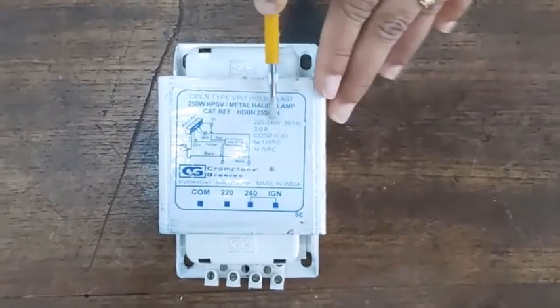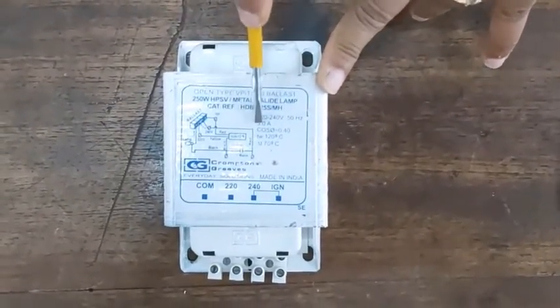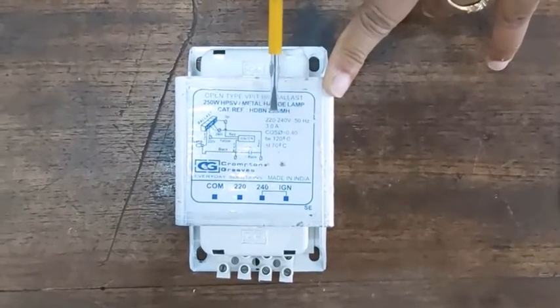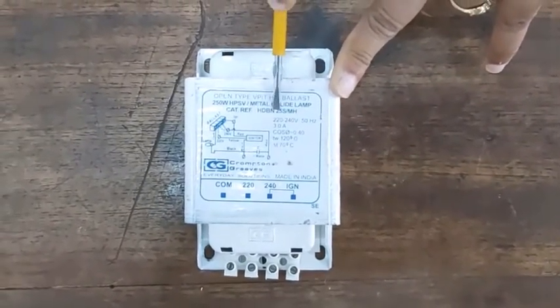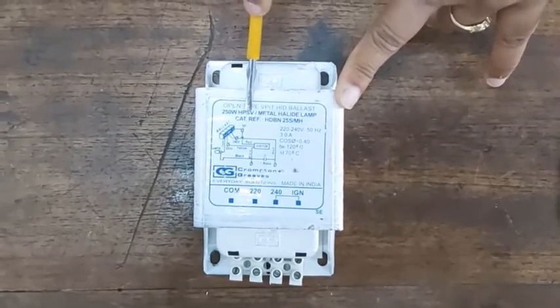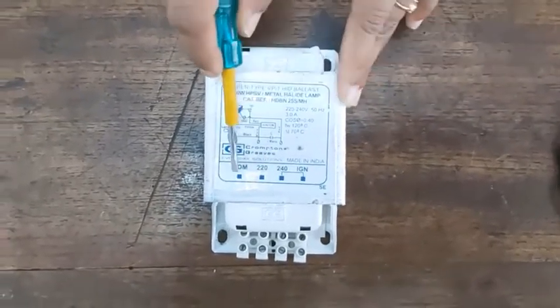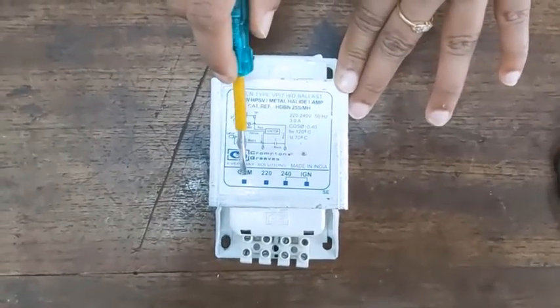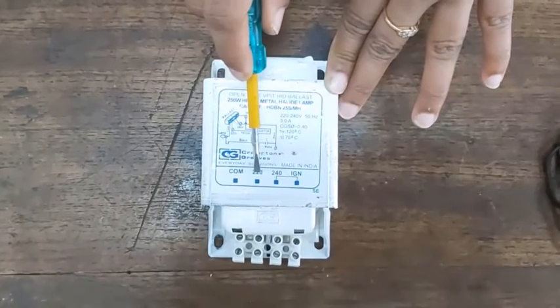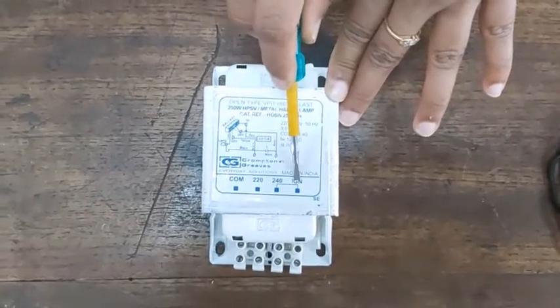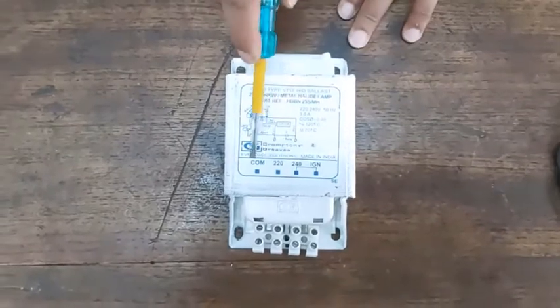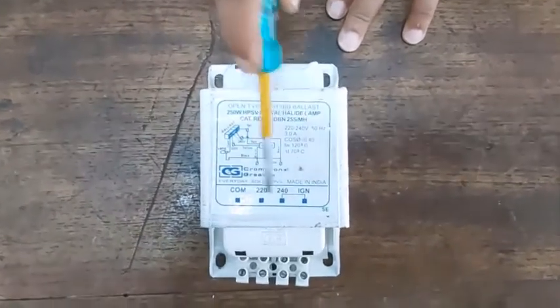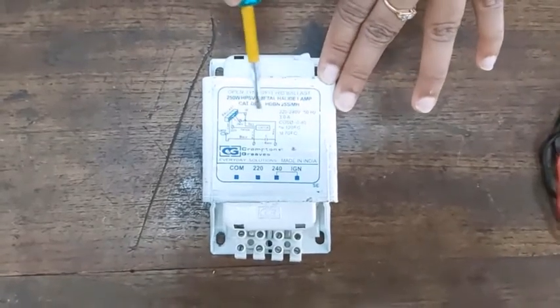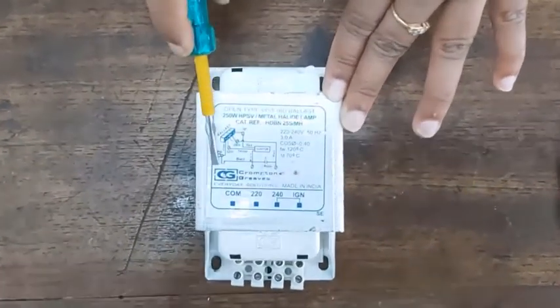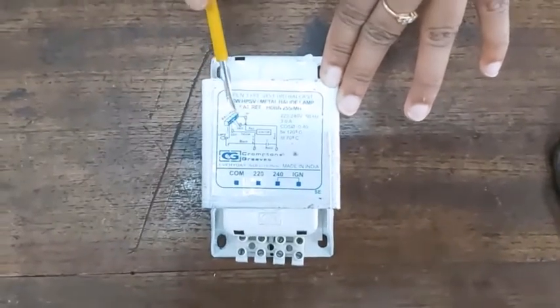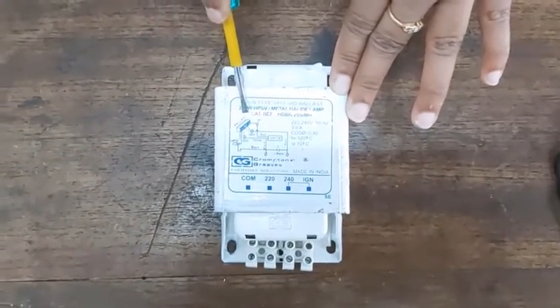This is a 220 or 240 volt 50 Hz choke. It is of 3.0 amperes and can be used for a 250 watt high pressure sodium vapor lamp. The terminals of the choke are provided here. It has 4 terminals: common, 220 volt, 240 volt, then one for the igniter. So depending on the supply voltage, we are going to select the voltage tappings. On this choke, the manufacturer also provided the wiring diagram of this high pressure sodium vapor lamp fixture.